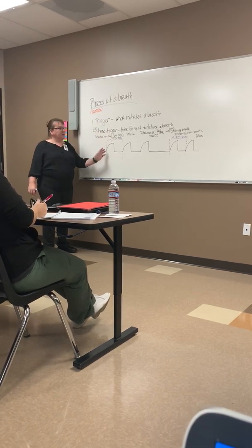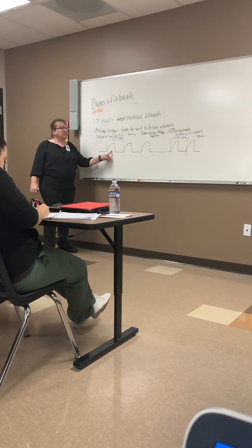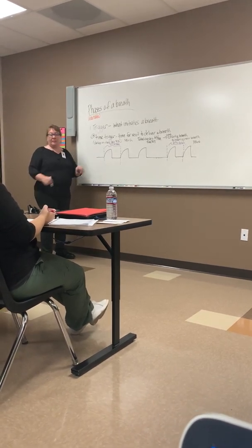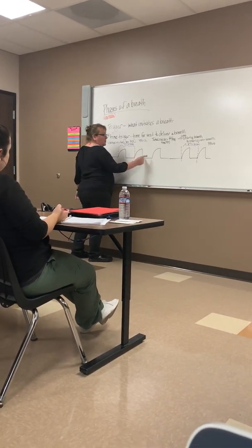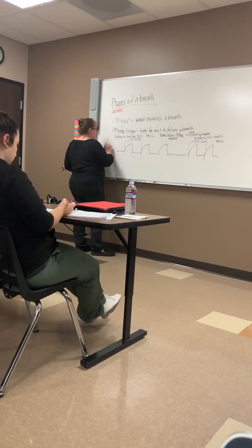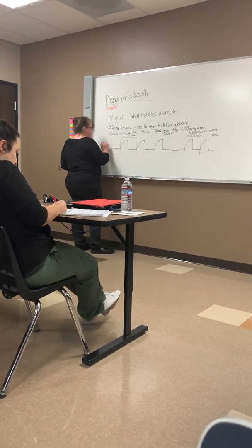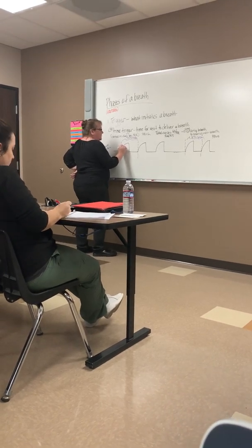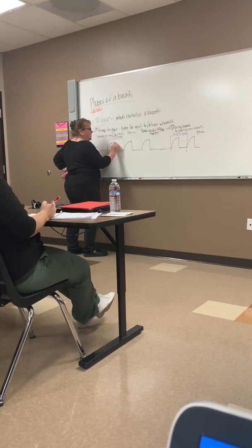So we're going to talk about the triggers, but I also have to talk about other things that fall within here so you understand how all this works. Within the total cycle time, I have inspiration and expiration happening. So the way I've drawn this out, this is inhalation, this is exhalation, this is inhalation, this is exhalation. You'll learn that this is a pressure waveform, but just so you know what we're looking at, that I've drawn here. This is what we know as inspiratory time, and this is going to be expiratory time.